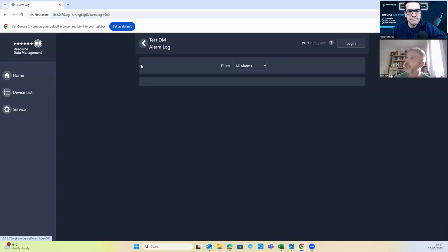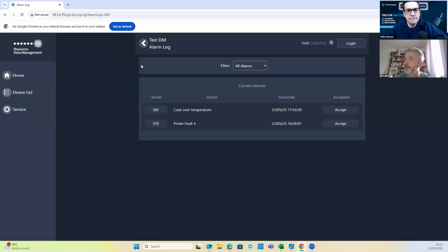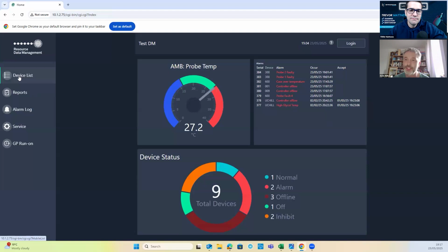If I go into the alarm log for this controller, it's also telling me I've got a probe fault. Now, because it's 2 foot away from me, I can see I haven't put the wire in. If you're out in the field and you're doing this, you're then going to be checking where that probe's connected to. Is the wiring properly? Has somebody stood on it and ripped the cable out? Standard, especially if it's a cabinet.